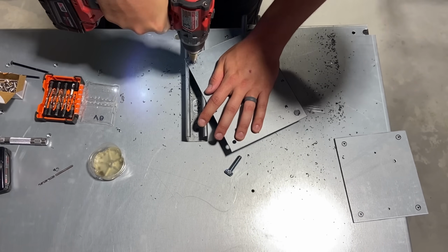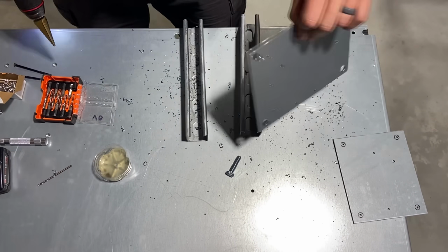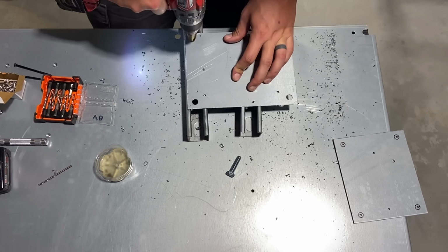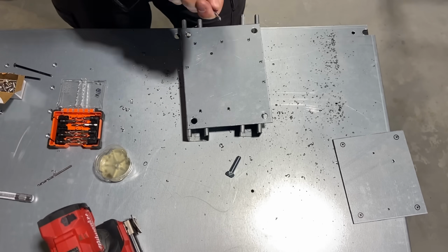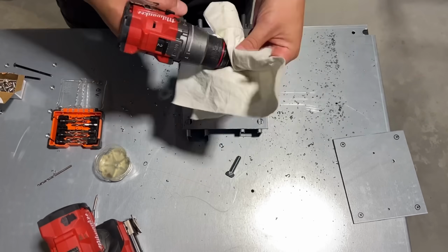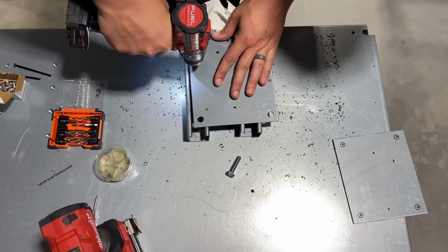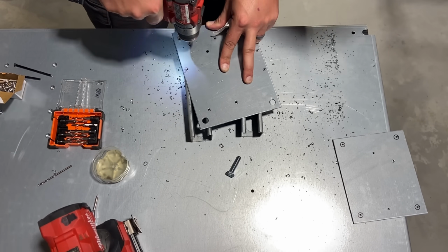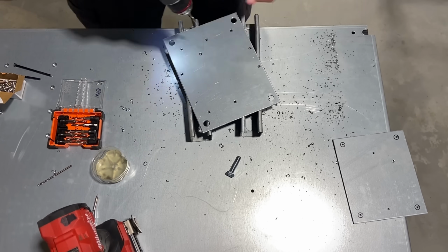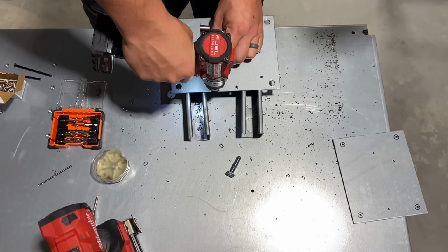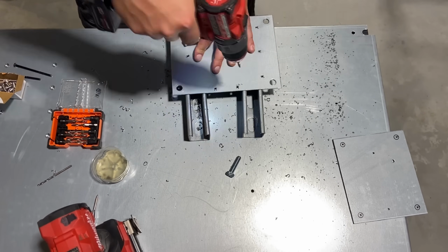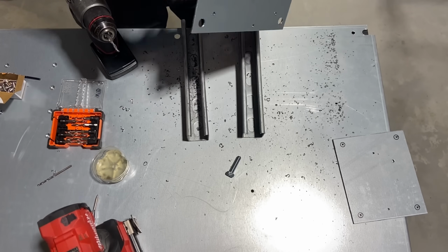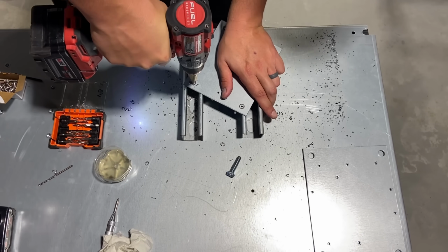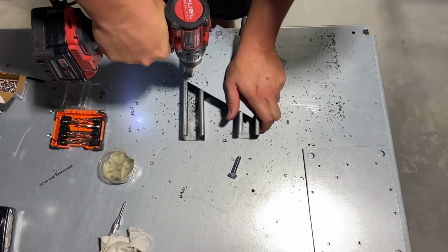Worst case scenario, I guess I could run a larger circuit out there, but because I'm changing the generator from 3-phase to single phase, I did get a little confused on what size the circuit breaker should actually be, and I'll be replacing the circuit breaker in the generator as well. So I essentially had to buy 3 circuit breakers for this generator: one in the generator, one when it comes into the house, and then the backfeed to the main panel, or the large panel, which is also 150 amps. So that should be more than enough.